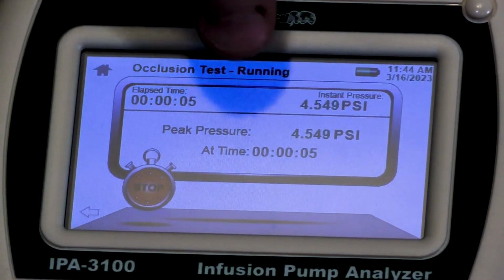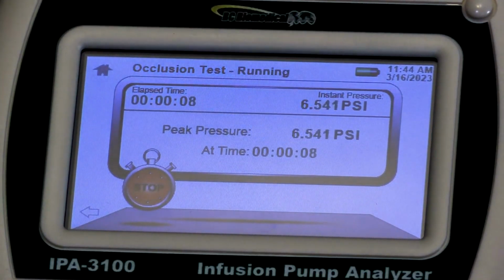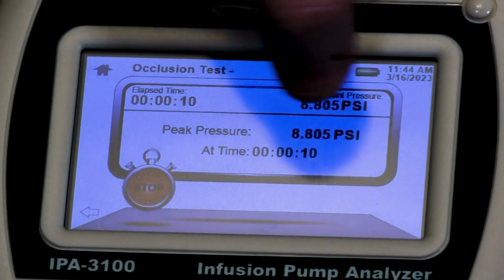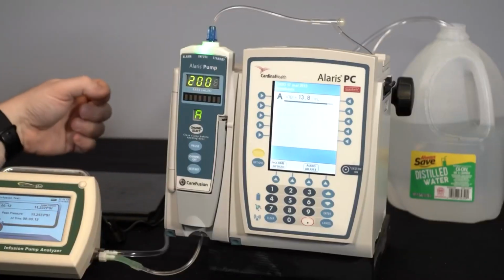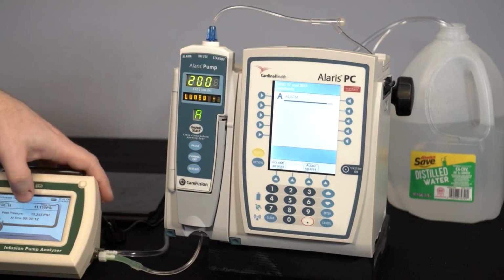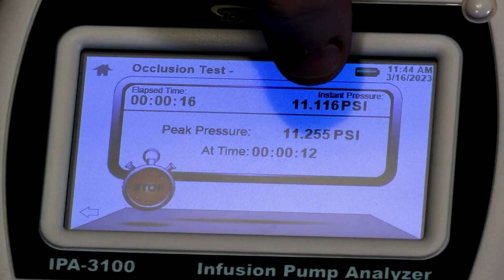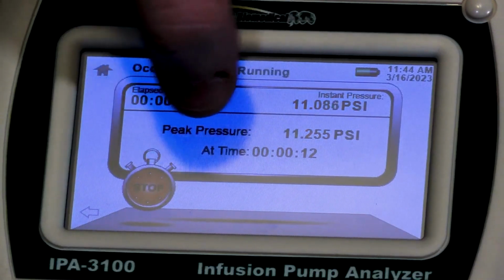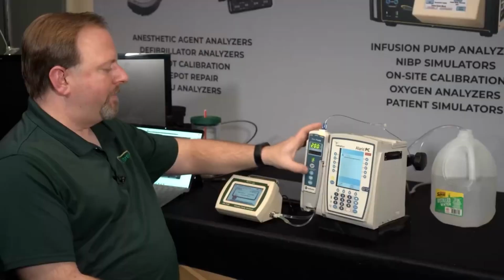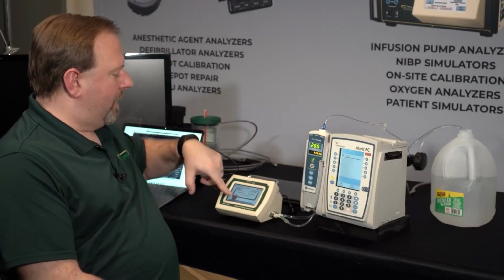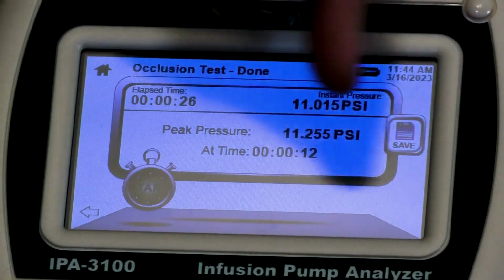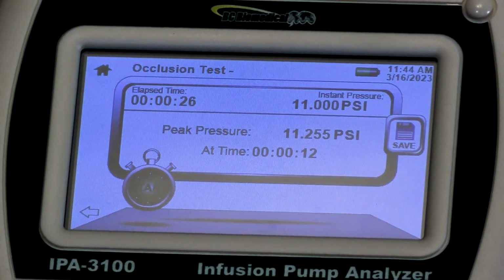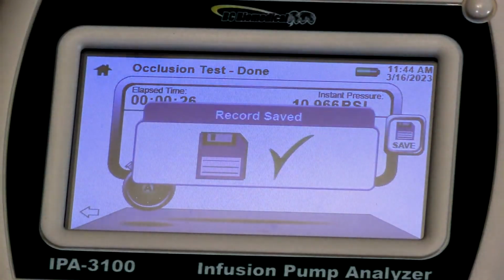And now it's going to tell us exactly when the occlusion occurs and the current pressure in the tubing. So there's our pressure. We can see the pump stop because the pressure is starting to decrease. It's showing me the peak pressure and how long it took to reach that peak. I'm going to stop the pump so it stops yelling at me. And then when I stop the test, now I have the option to save. Again, I have the unit set to manual save, so it won't save every single record that I perform, but I do like this one, so I'm going to save the record.